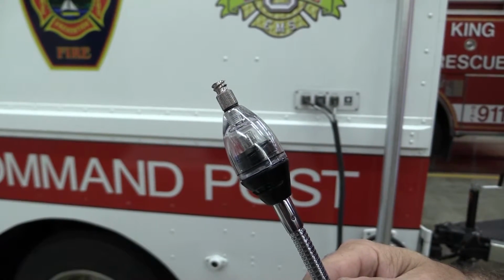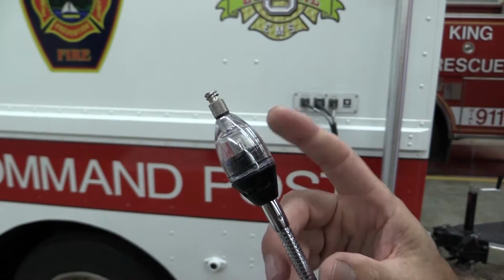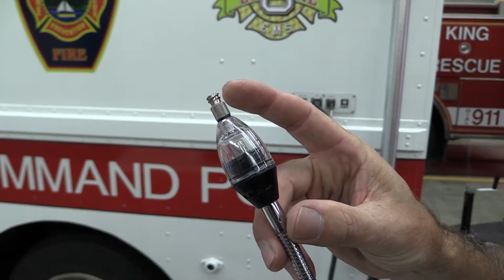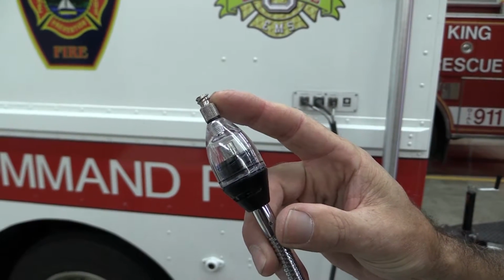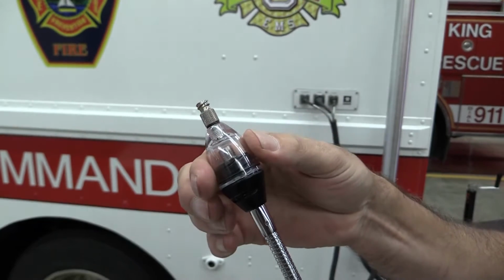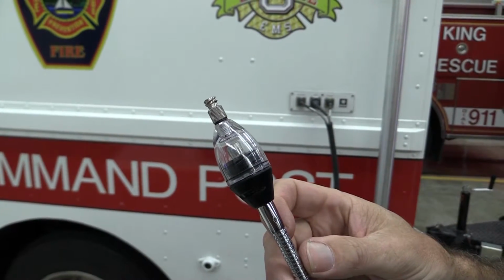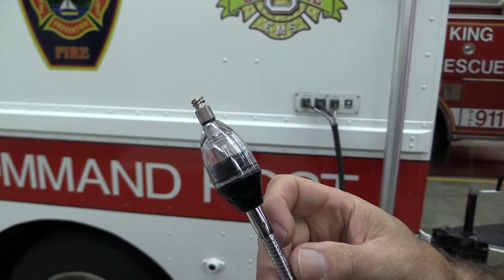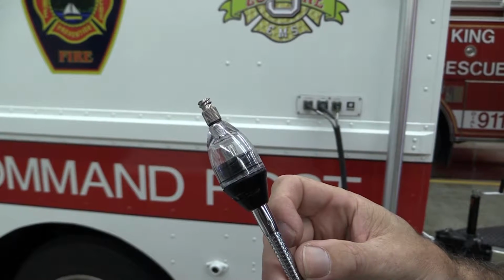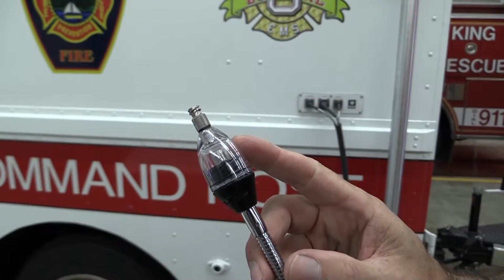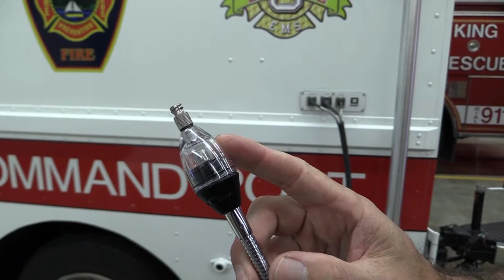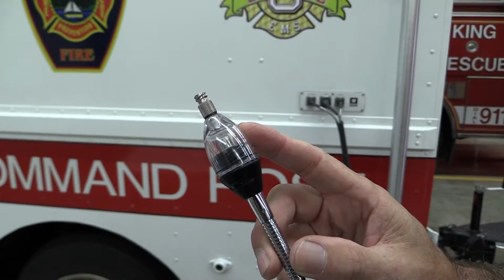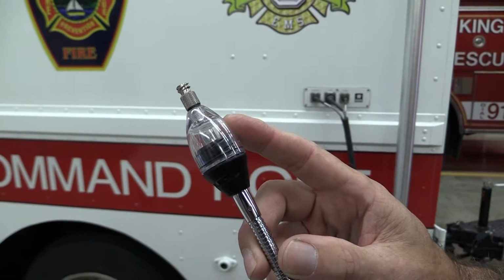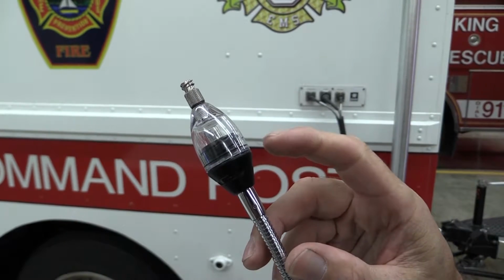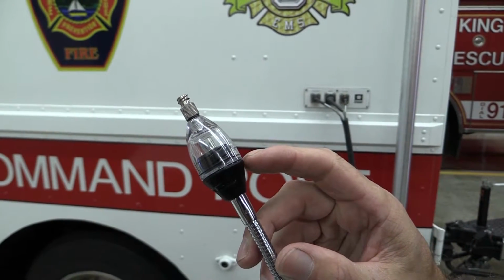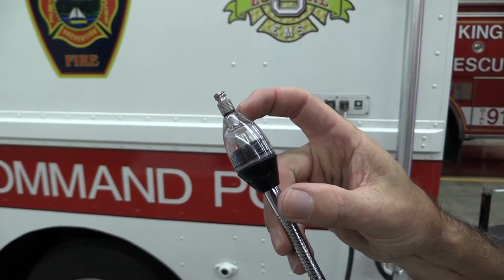Before turning the unit on, check that the plastic filter cap and the metal connector are both firmly tightened down and have their O-rings in place. A good air seal at these points is essential for proper operation. If there's ever damage to the plastic filter cap, remove it and install the replacement cap found in the box, making sure that the included O-rings are used in the correct places, with the larger O-ring here and the smaller O-ring here.